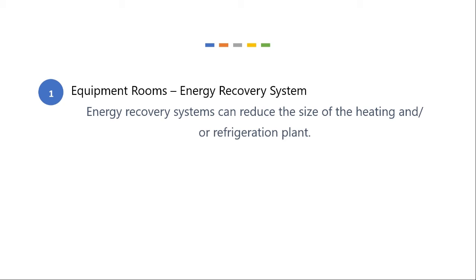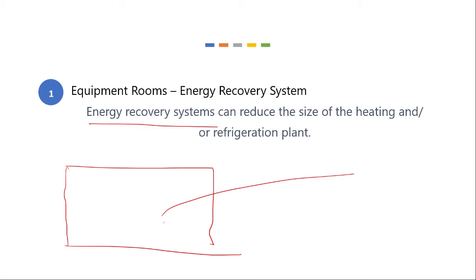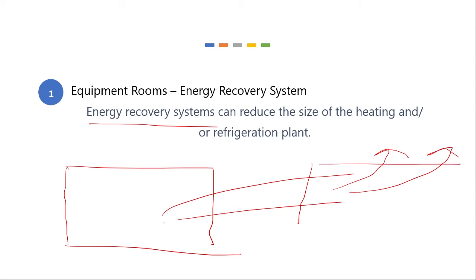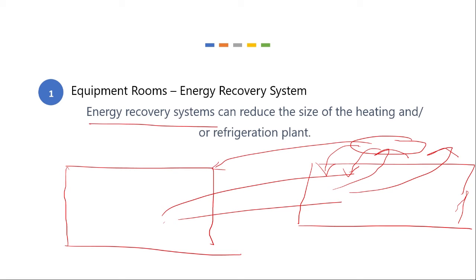So what's also popular, and we'll look at this later, are energy recovery systems. They can reduce the size of your heating or refrigeration plant. The way they work is you're producing heat energy based on whatever capacity to your building, and all of this heat is leaving to the environment. So you can put in a system that recaptures some of the heat and either puts it back into the building or sends it back to your plant, and your plant will capture the heat and send it back, and that cuts costs.